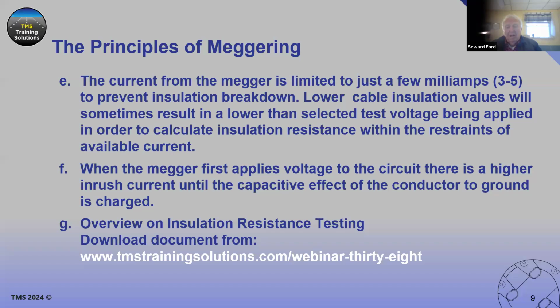And so in that case, we're not able to get a particular megger reading for that particular voltage on that particular cable. When the megger first applies voltage to the circuit, there is a higher inrush current until the capacitive effect of the conductor to ground is charged. The dielectric, the insulation covering on the conductor, depending on what shape it's in, will build up a voltage there on the inrush current, and it has a capacitive effect on the conductor. How quick that happens depends on the quality of the cable insulation that we're testing.